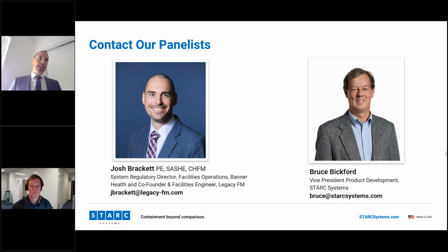You are permitted in NFPA 72 to use heat detectors in lieu of smoke detectors where the environment is not suitable for smoke detectors. So what I would do is document that there would be significant dust and that you are using the option to use heat detectors in lieu of smokes. However, I would also caution you on that because smoke detectors can be managed properly in construction environments by covering them up during the day when you do have people there, and vacuuming and dusting them off before you put them back in service again.